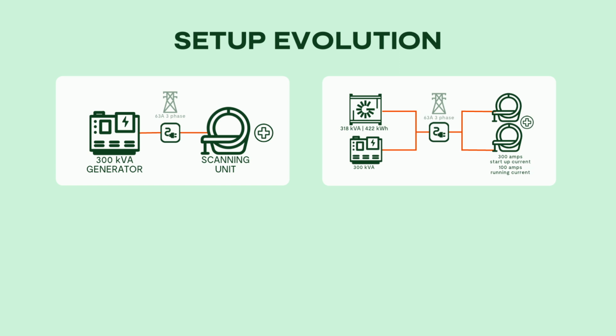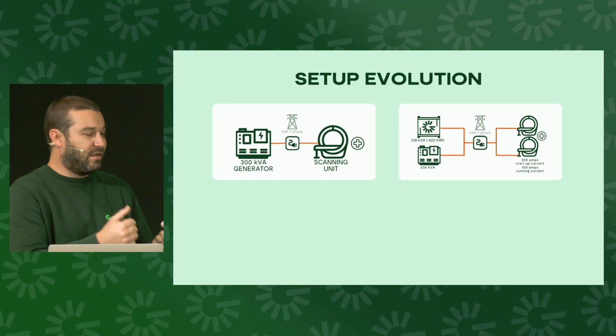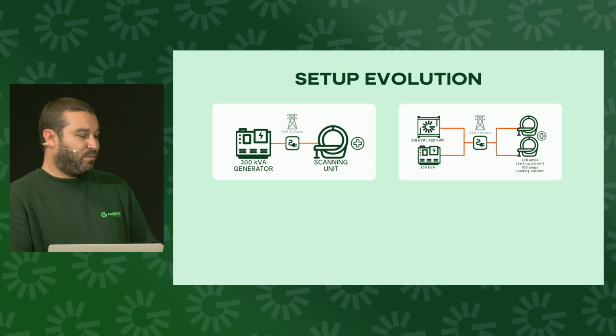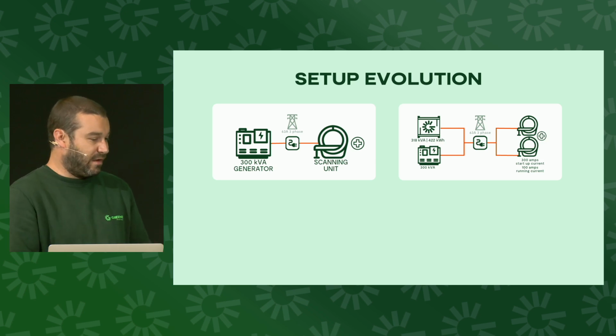At the same time, a second scanner was added, so we now had two loads with potentials of up to 300 amp inrush currents each. By hybridizing the generator with a battery, we were able to provide the potential of 600 amps by utilizing the generator and battery together, since we've got a battery capable of 400 amps and a diesel generator capable of 350 to 400 amps itself.